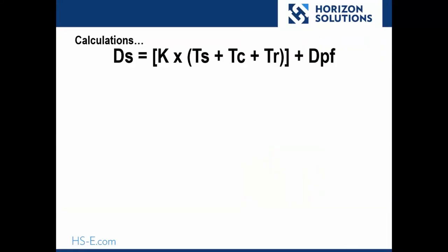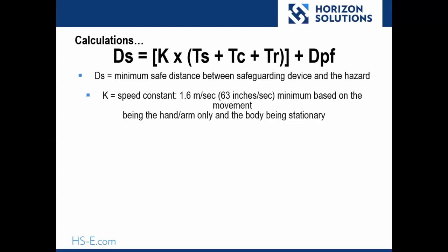Here we have the equation for creating the safe minimum mounting distance according to the ANSI standards. DS is the minimum safe distance between the safeguarding device and the hazard itself. K is the speed constant given at 63 inches per second according to the standards, and this is for the average hand or arm speed.